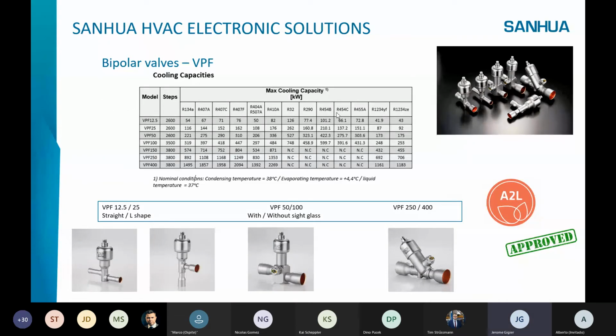So in the catalog, in the datasheet, you will find the selection table for the main refrigerants, not all, because there are many more refrigerants. But for R32, for example, you can see what we have certified, and NC is not certified, so we can use the R32 VPF for R32 till 750 kilowatt. So it's already a huge possibility. We have also propane, and the standard refrigerant, 410A, for example, that you know perfectly for many years. So we can reach 2 megawatt with 410A with the big valve.